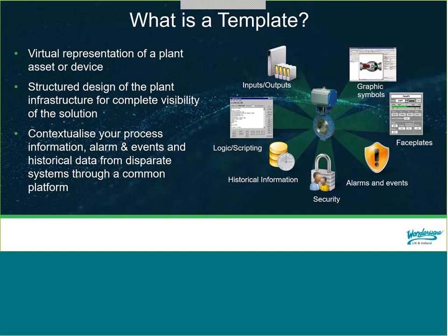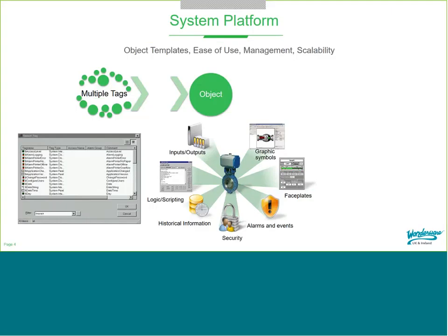Everything's contained within the same environment, and what that means is you can have very rapid deployment from a scalability perspective, or certainly rapid change management, because if you create lots of instances from that template, and then you want to change all those instances, you make it at template level and it propagates through to the rest of them. It's a very neat way to work, it's a very structured approach, and this is, I suppose, how it differentiates between a simple tag-based solution and an object-based one.